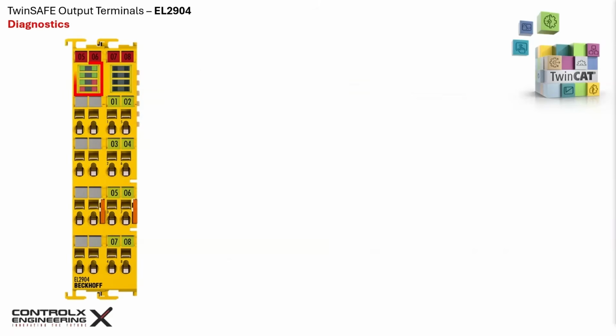The EL2904 uses signal LEDs on the left half of the terminal to give you immediate visual feedback about the state of each safe output channel. Each of the 4 safe output channels has its own LED, and these LEDs reflect the output on-off state. The terminal also has 4 diagnostic LEDs. If the terminal detects a wiring issue such as short circuit, cross circuit, or abnormal current draw, the LED may flash or switch to a fault indication pattern. This works together with the EL2904's integrated current measurement and output testing features. If the terminal enters a fail-stop state due to an internal or external safety fault, the LEDs help identify which channel has triggered the issue.